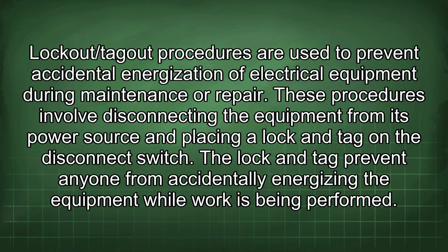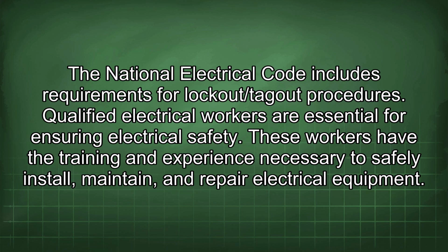Lockout/tagout procedures are used to prevent accidental energization of electrical equipment during maintenance or repair. These procedures involve disconnecting the equipment from its power source and placing a lock and tag on the disconnect switch. The lock and tag prevent anyone from accidentally energizing the equipment while work is being performed. The National Electrical Code includes requirements for lockout/tagout procedures.